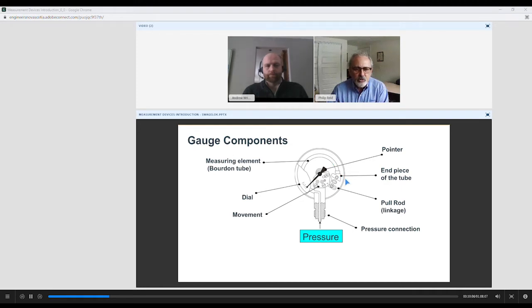On the end of the Bourdon tube is an end piece, which has a mechanical link or pull rod in here, and this goes to the movement, and the movement is pinion gears, springs, and segment gears. These movements are actually made in Switzerland. For those of us who have been around long enough when mechanical watches were still very popular, like a Rolex, the mechanical movements are made in Switzerland actually for these gauges. So they're sensitive. You don't like to drop pressure gauges. It can throw off the accuracy. It can do a number of things. Actually jump gears, and the springs can be damaged as well.